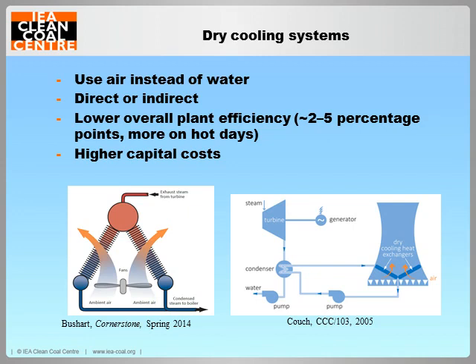Indirect dry cooling is shown in the figure on the right. Here, the steam is first condensed in a conventional water-cooled condenser, and then the heat is conducted from the warm water as it flows through fin tube heat exchangers in the dry cooling tower by the upward flowing ambient air. There's no evaporative water loss since it's a closed system.